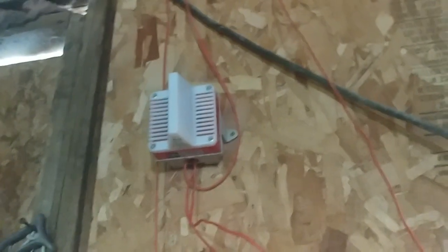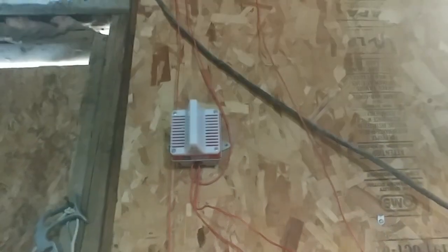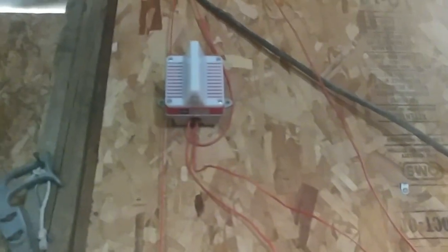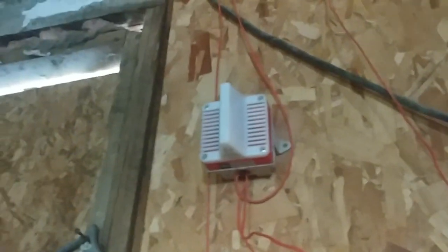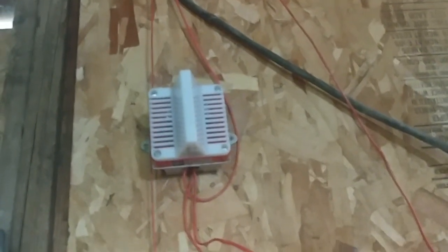I'll tell you what, this is a thing that does not sound too healthy, to be honest. This horn strobe definitely needs surgery. That's the thing with these motor horns — they don't really sound that great. Apparently this one actually sounds quite alright; it sounds kind of like a regular electromechanical horn on fully rectified current. This panel does output filtered DC, but it still sounds really raspy because it's a motor horn. If you put this on FWR power it's gonna sound the same — nothing special.